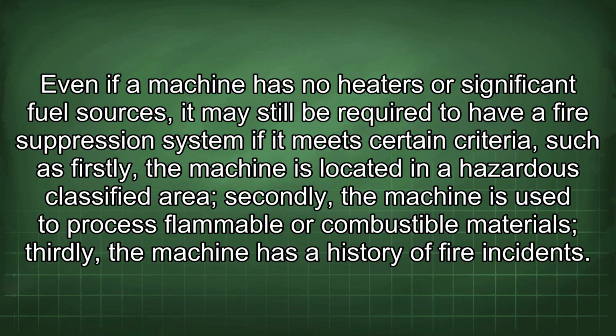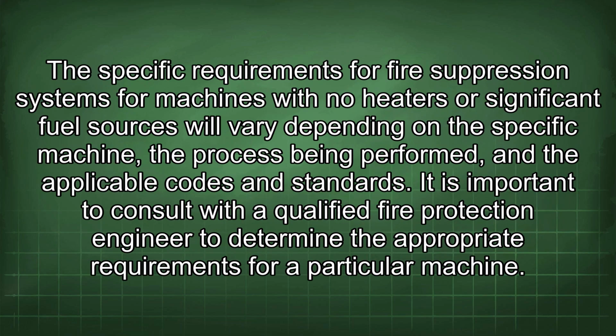Even if a machine has no heaters or significant fuel sources, it may still be required to have a fire suppression system if it meets certain criteria, such as: firstly, the machine is located in a hazardous classified area; secondly, the machine is used to process flammable or combustible materials; thirdly, the machine has a history of fire incidents. The specific requirements for fire suppression systems for machines with no heaters or significant fuel sources will vary depending on the specific machine, the process being performed, and the applicable codes and standards. It is important to consult with a qualified fire protection engineer to determine the appropriate requirements for a particular machine.